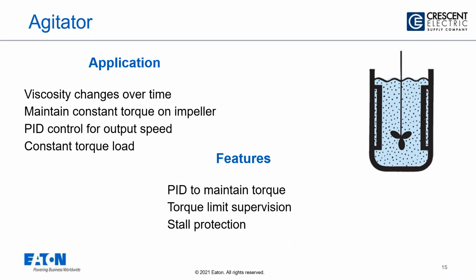And in most blenders and mixers, the viscosity of the fluid or the contents of the mixture changes with time, but the application requirement is to maintain a constant torque or constant power. So when the viscosity is low, the impeller will run faster, and when the fluid becomes thicker, it will automatically regulate. The PID will regulate to run the impeller slower. So there is a PID control, and that is what is being used, and I'll tell you how it is set up in order to do this. We also have torque limit supervision and stall protection. All the features are built into both the drives, or most of our drives. Next slide, please.